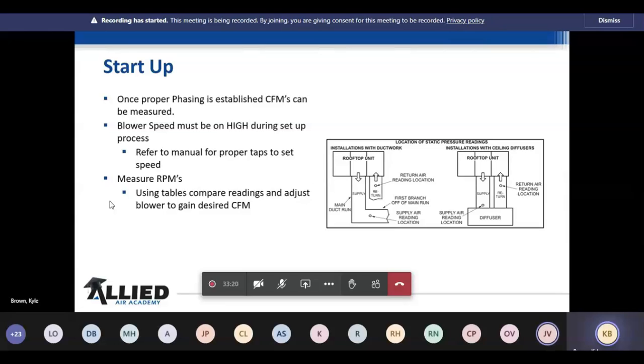So there's all kinds of things, but making sure you're in a good location, making sure you know how they check the static, what the state of the unit was in. I like to check them with wet coils. You get a true, accurate representation. I also like to check them with the filter that you're going to use, okay? If you're going to use a higher MERV filter, don't leave the factory blue filter in there. Set everything up and then put a higher MERV filter in there, because that's going to throw everything else off. So there's a lot of stuff to be considerate of whenever you're checking these to make sure you're good to go on it.